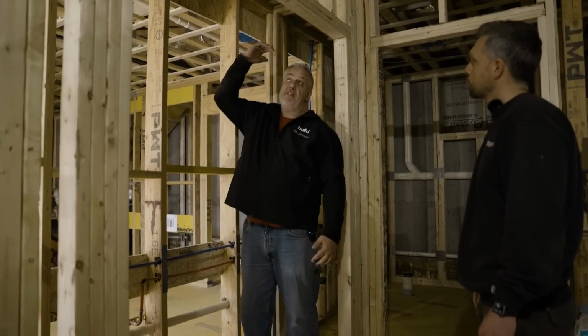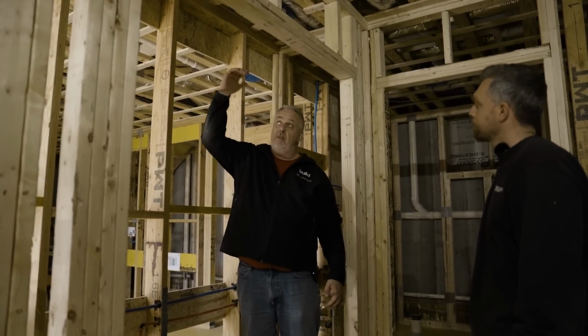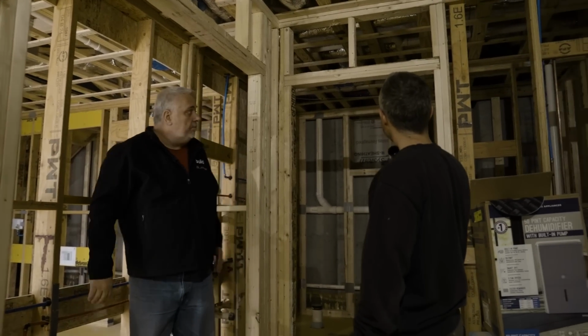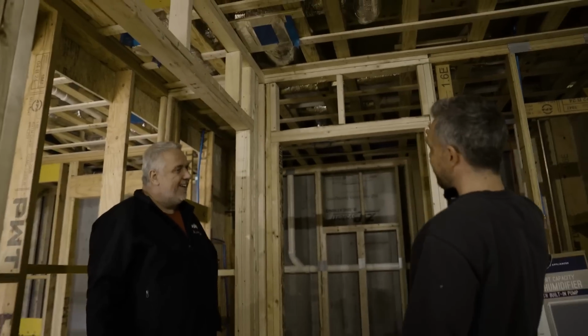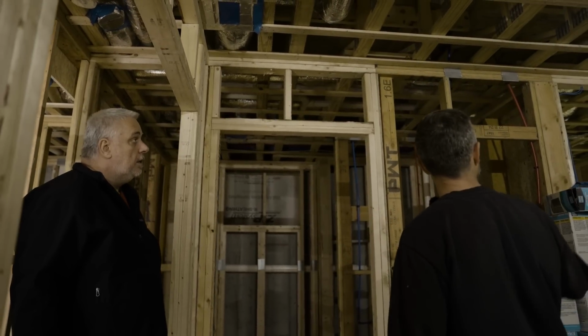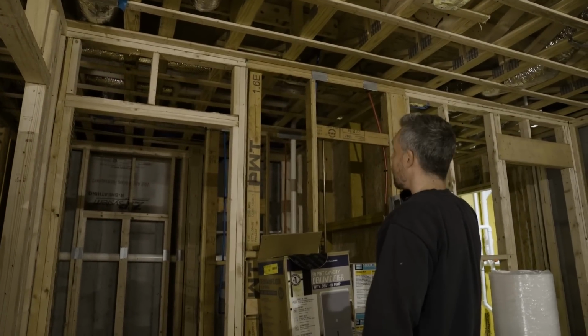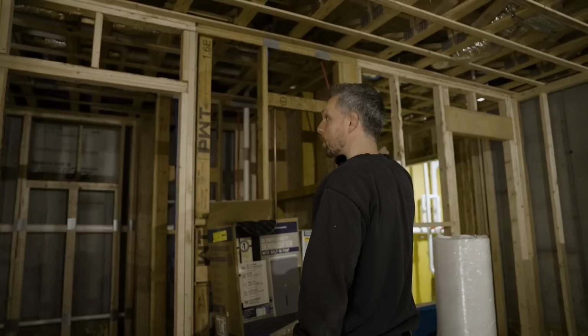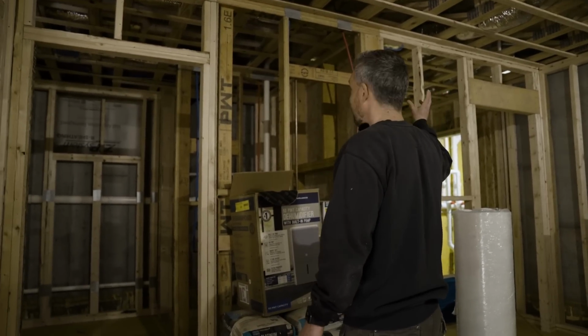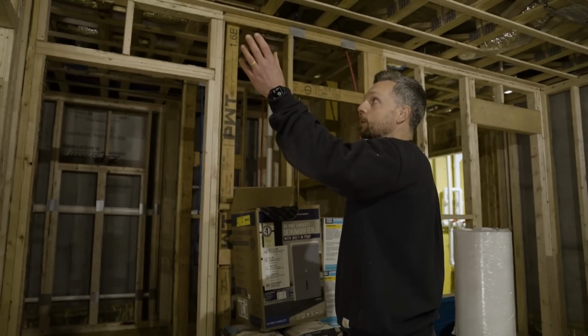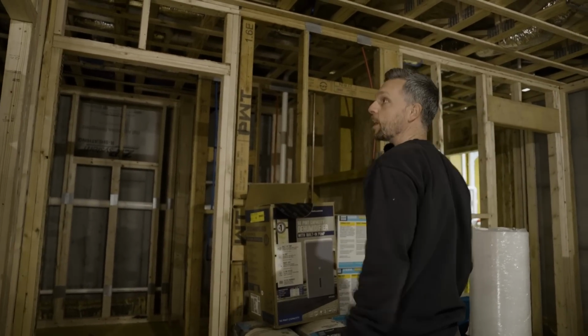And because we're in a confined system here in this 900 square foot unit, all of this is happening in the head of the closet. It's a pretty shallow unit, above the doors, and you'll be able to exchange the filters nice and easy. It's here instead of the mechanical space because there's some knuckle-busting work to get all of this to fit into the small space, and it all converges in our mechanical room. So to have fewer runs of ductwork going in there and figure out where to poke out to outside, it made more sense to put it here rather than funnel into that bottleneck.